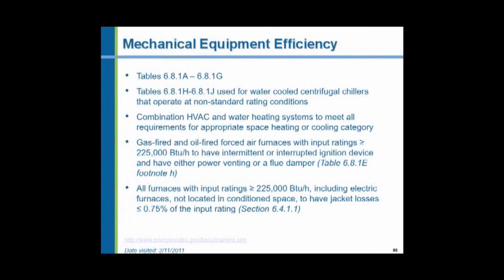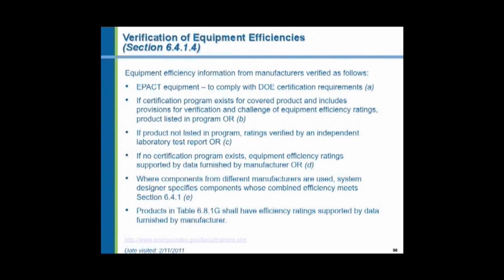Furnaces with input ratings greater than 225,000 BTUs per hour cannot have any kind of a standing pilot light for the ignition source. It has to be something spark or some kind of a glow coil ignition. They have to have some kind of jacket insulation in the sheet metal housing of the unit. For equipment efficiencies, the Energy Policy Act, EPACT, requires the appliance to comply with the DOE certification requirements. That is one program.